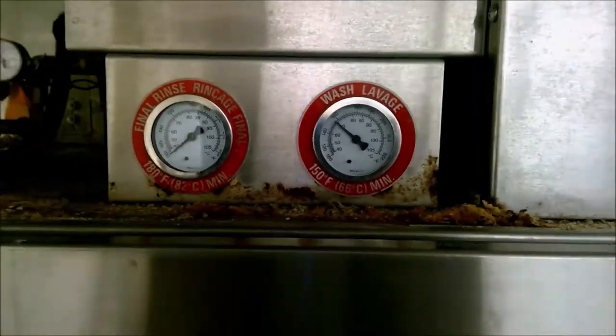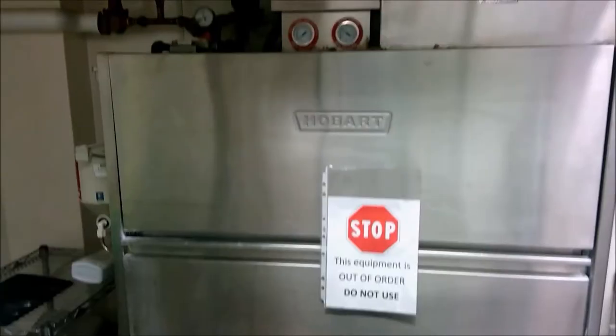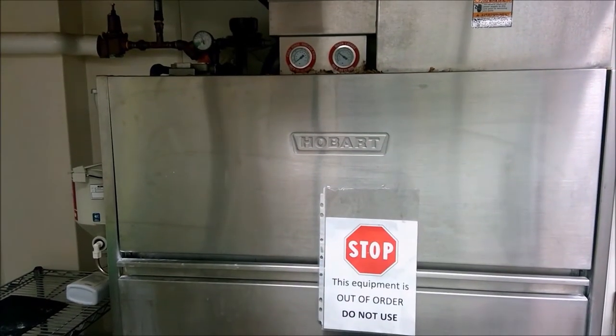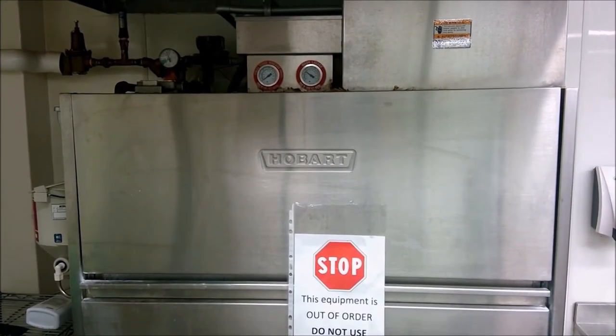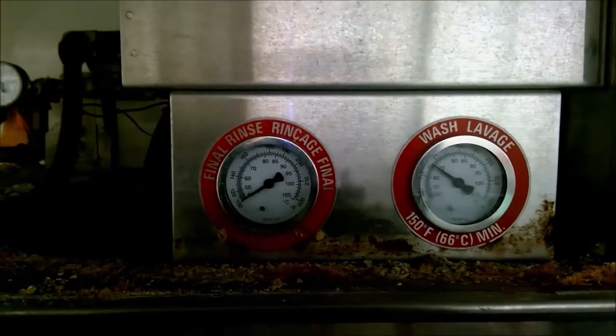We're going to run another cycle here and try to figure out why this high limit tripped. We're only getting to 168. I'm just going to hit fast forward here, run a couple cycles and let's see what happens.